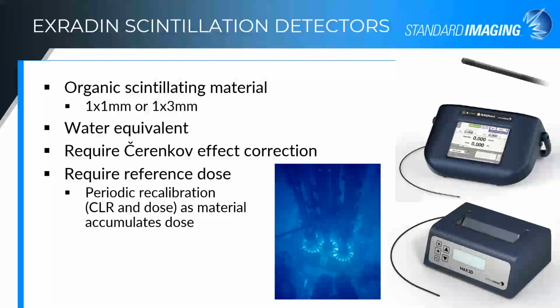Ours are an organic scintillating material, BCF12, that is coupled to a PMMA optical fiber. The active region, depending on which of the scintillators you're talking about, is either 1 millimeter diameter, 1 millimeter long, or 1 millimeter diameter and 3 millimeters long. So what we call the W1 is the 1x3. The W2 has dedicated electronics and a user replaceable fiber, and you can have either the 1x1 or the 1x3.